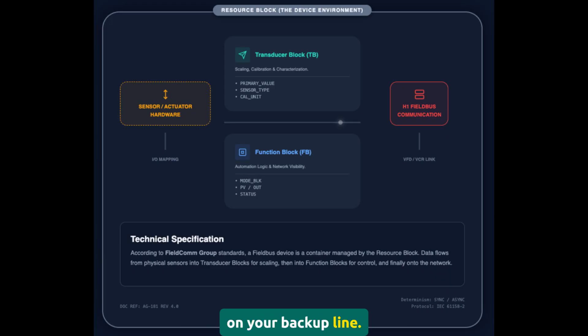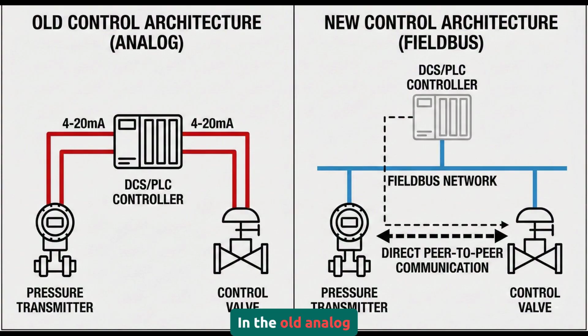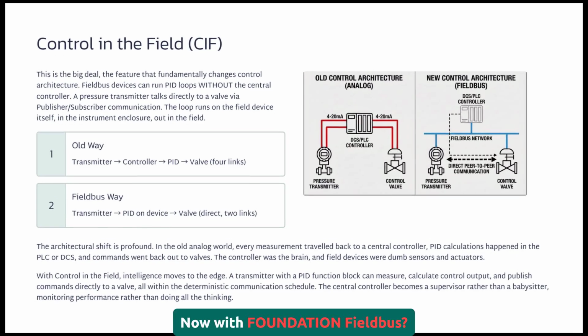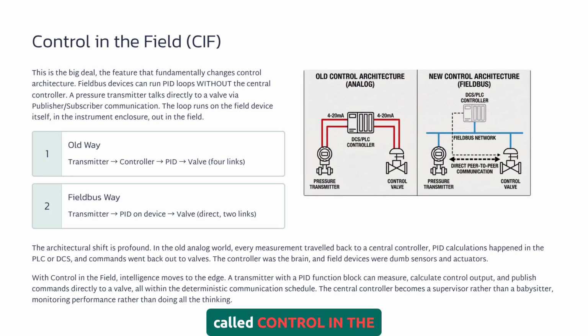Alright, so imagine you've got a pressure transmitter on your discharge line, and you've got a solenoid valve on your backup line. In the old analog world, you're pulling that pressure signal back to a PLC or a controller. The controller's running a PID loop. The controller decides whether to open or close the valve. The command goes back out. Now with Foundation Fieldbus, you can do something called control in the field, CIF.